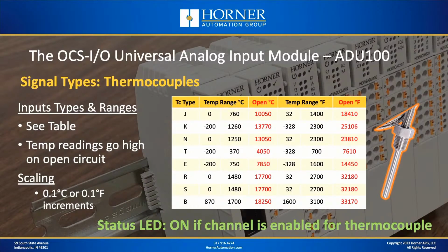Next, let's talk about the signals or the values that are being reported by the ADU100. Those values are going to vary by thermocouple type, at least the range of values that are supported. And you can see on the screen there 8 different thermocouple types that are supported by the ADU100 and the temperature ranges that are supported in both degrees Celsius and degrees Fahrenheit. And then in the red columns, you will see the decimal values that are reported by the module if you have an open circuit condition.